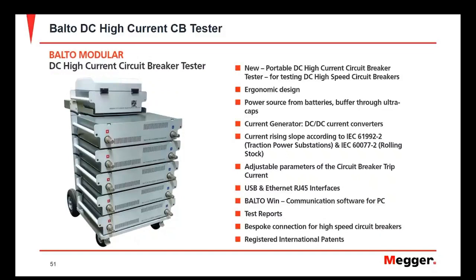The Balto is a DC high current circuit breaker tester. It operates by battery power assisted by ultra-capacitors, charged before going out in the field. The Balto provides a high-current DC output to test DC high-speed circuit breakers, delivering that power-dense output very quickly to test those high-speed circuit breakers within the required validation time. This instrument is compliant with IEC 61992-2 for testing high-speed DC circuit breakers and operates with the Balto Win software for easy user interface and test report production.